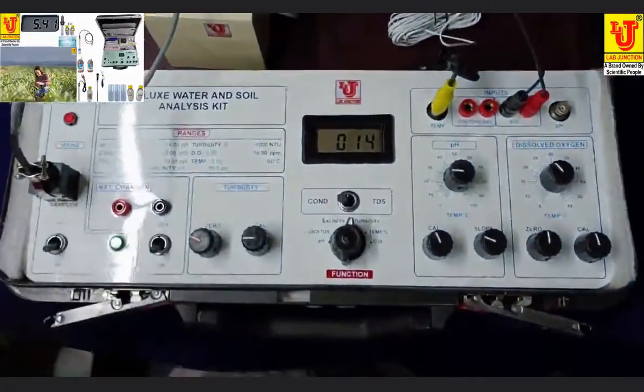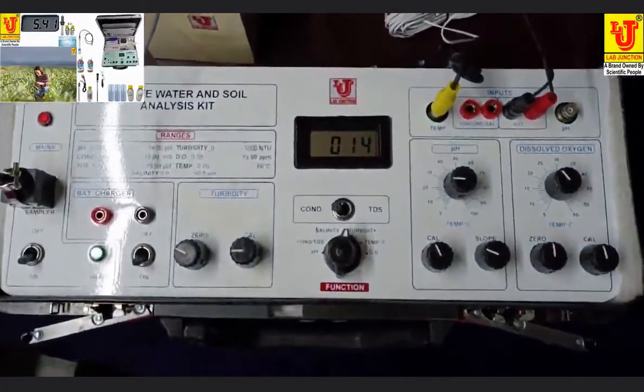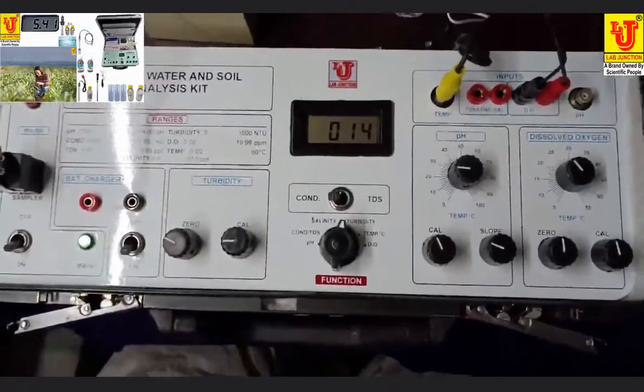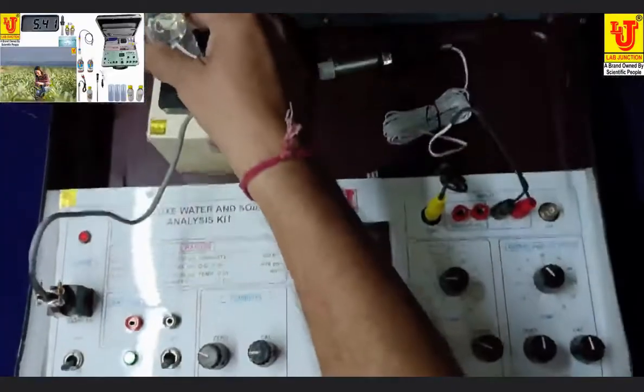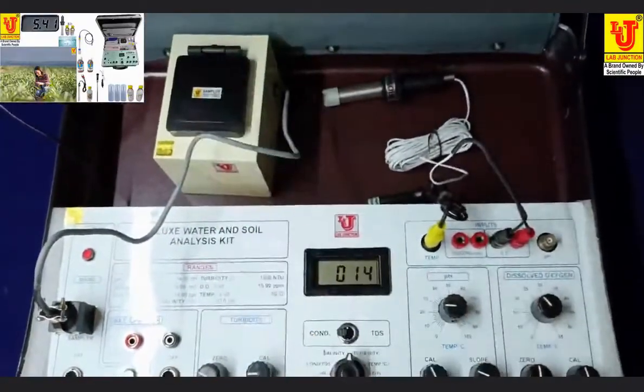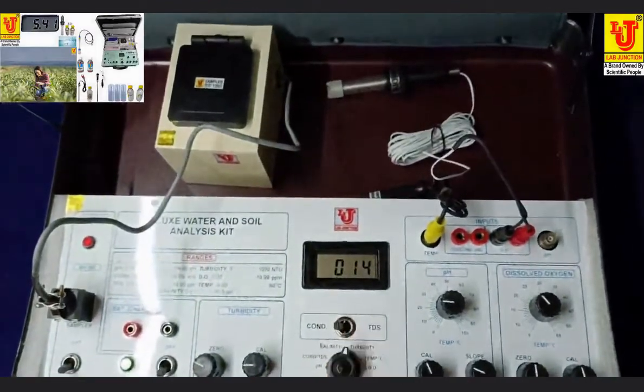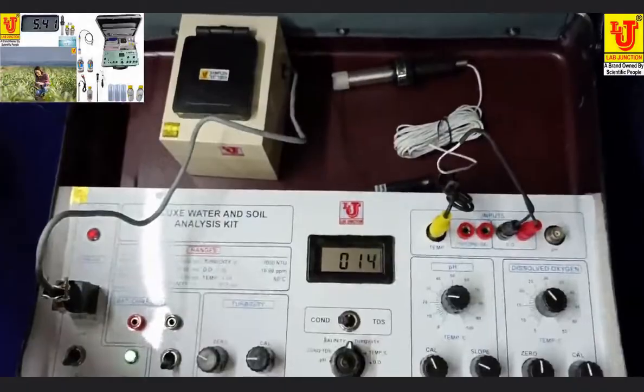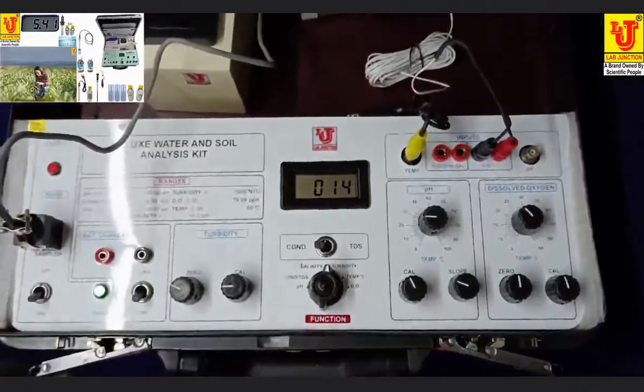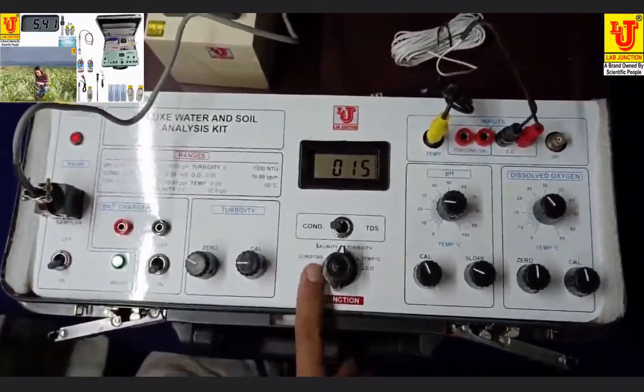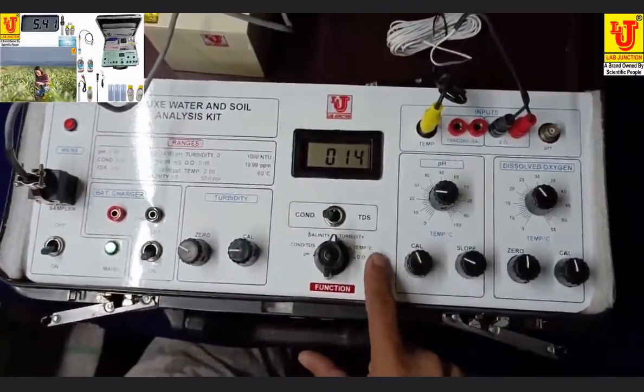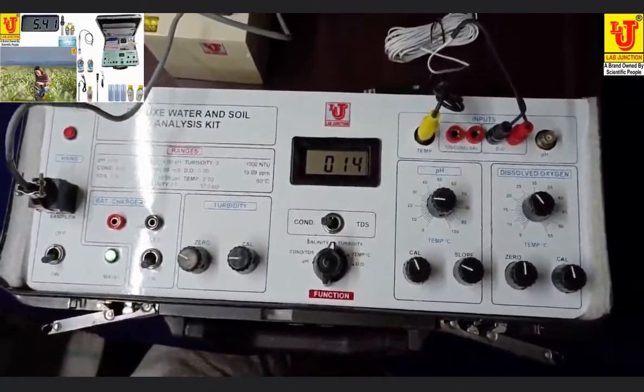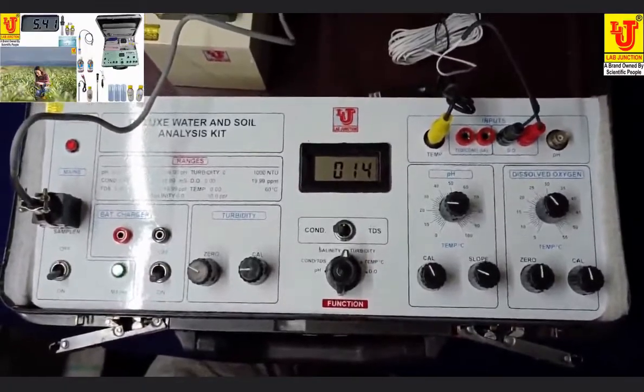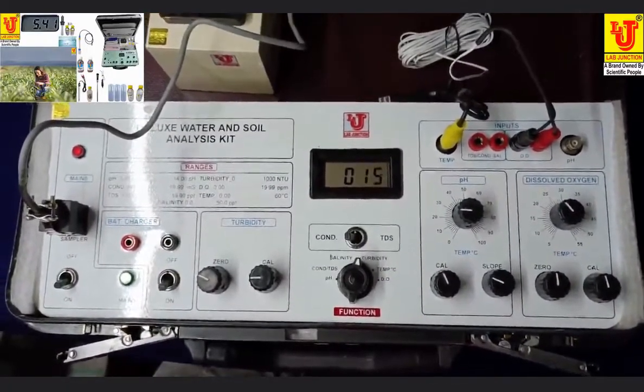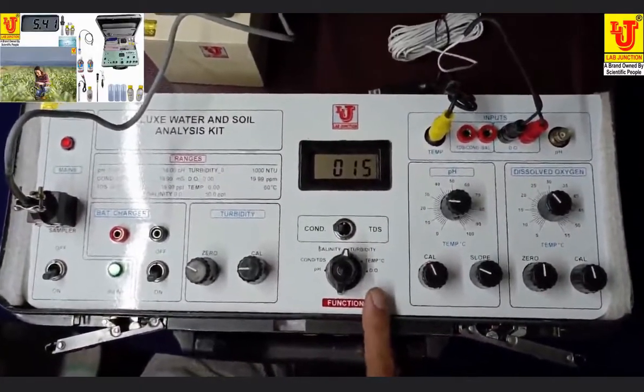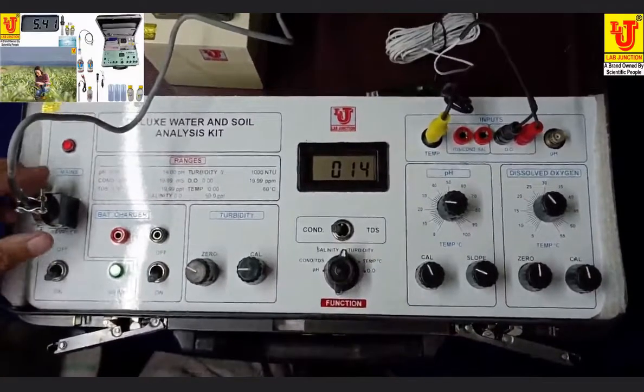Now my turbidity parameter is calibrated and ready for use. You can take a sample in this vial, insert it in this sampler, and it directly shows the turbidity measurement on the display. This is all for the turbidity parameter. Now pH, conductivity, TDS, salinity, turbidity, temperature parameters are all verified. Now we are going to the parameter dissolved oxygen. I am disconnecting this.